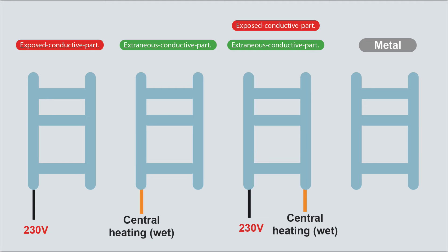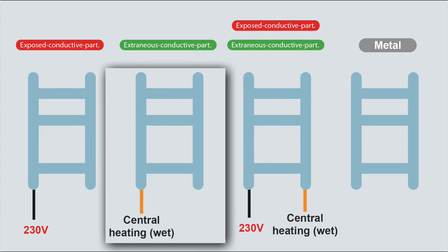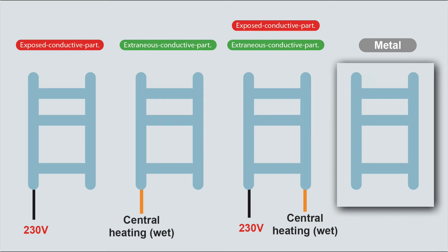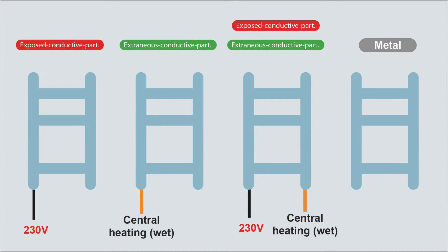I'm using the example of a towel rail here because that could be an exposed conductive part. It could be a purely electric towel rail connected to the 230 volt supply, or it could be connected to the wet system - the central heating - then it could be an extraneous conductive part. Or it could be dual fuel - electric and wet - and it could be an exposed or extraneous conductive part. Or it could just be a metal towel rail on the wall, not connected to the supply, not connected to any pipework - purely just a piece of metal. So we need to be able to prove, if we think it's just a piece of metal on the wall, that it can't introduce a potential. It's quite easy to see if it's an exposed conductive part - there's any power going to it. It's a little bit more tricky to know if it's an extraneous conductive part, and there's a test we can do to find that out.